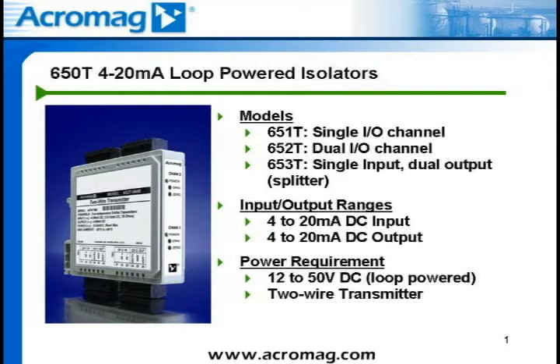Process current inputs are 4 to 20 milliamp DC analog signals. These isolated transmitters offer reverse polarity protection and a small input voltage drop of 1.5 volts DC per channel on the 651T and 652T, and 3 volts on the 653T signal splitter.